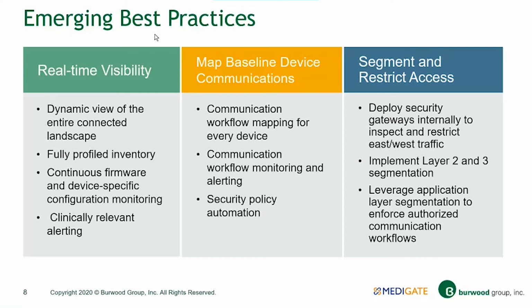Then moving to that mapping communication baseline, the matrix you were just showing is critical if we're going to build a zero trust environment. And that's really what we're after for medical device protection, is building that zero trust. These devices have very limited communication needs. It's very clear who they're supposed to talk to and who they're not. The network should support that and should block that. There should be no reason that those devices are communicating with anything they shouldn't be.